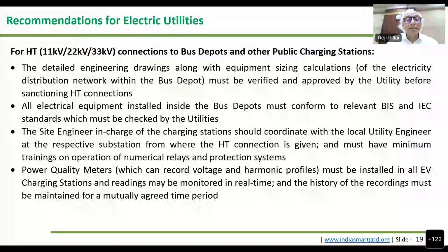Power quality meters which can record voltage and harmonic profiles must be installed in all EV charging stations with more than a few hundred kilowatts of load given. The readings may be monitored in real time, and a history of the recordings must be maintained for a mutually agreed time period.